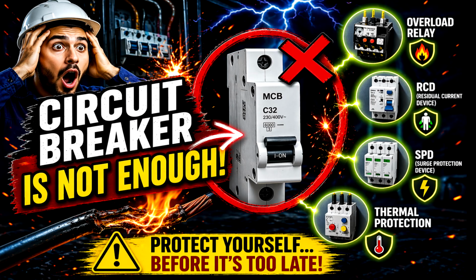Third type, miniature circuit breaker, MCB. This is the standard breaker, but we must understand it correctly. Magnetic part trips instantly during short circuit. Thermal part trips during overload. But still not enough alone in many cases. Fourth type, surge protection device, SPD. Many people forget this. It protects against lightning strikes and sudden voltage spikes, which can destroy appliances, screens, and electronic boards in a single moment.